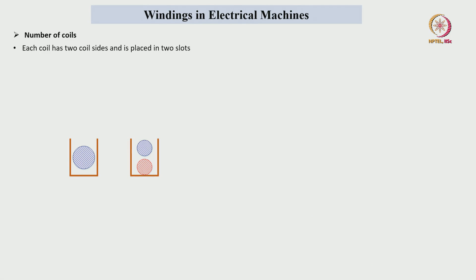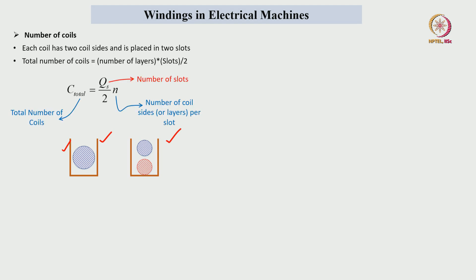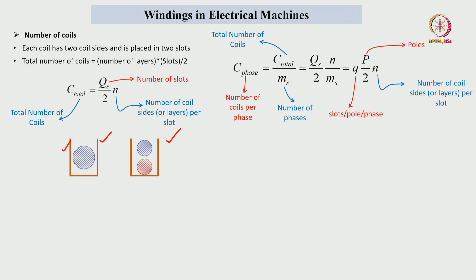The number of coils depends upon the number of slots inside the stator core and how many coil sides are in each slot. If one coil side is in the slot it is single layer; if two coil sides, it is double layer. The total number of coils is calculated as Qs divided by 2, multiplied by the number of coil sides or layers per slot. The number of coils per phase, C_phase, is the total coils divided by the number of phases M. This gives the final expression in terms of slots per pole per phase Q, number of pole pairs P/2, and number of layers N.